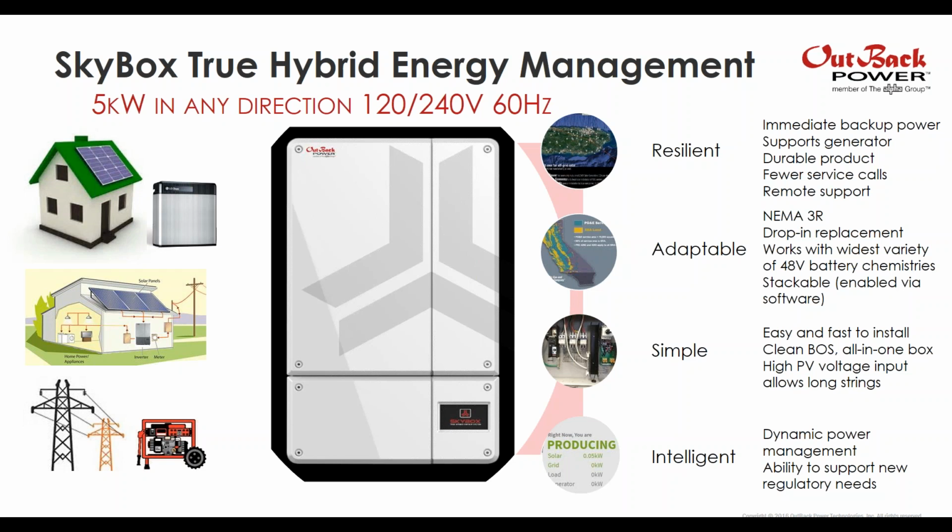So SkyBox is adaptable. It's NEMA 3R, so it's a drop-in replacement for existing grid-dependent string inverters, and it works with the widest variety of 48-volt battery chemistries, and we'll talk more about that later too. But it supports lithium-ion as well as the lead-acid batteries. And then SkyBox is stackable, and that's just enabled via software.